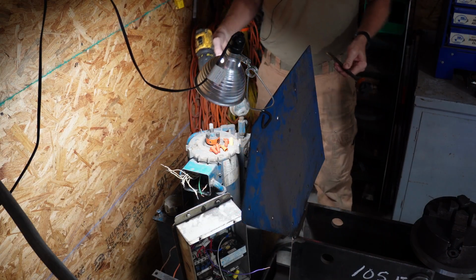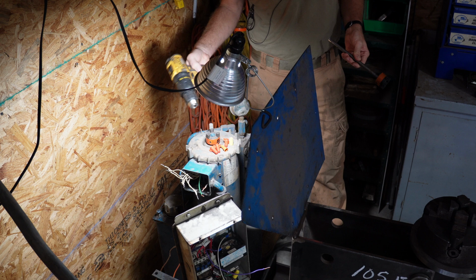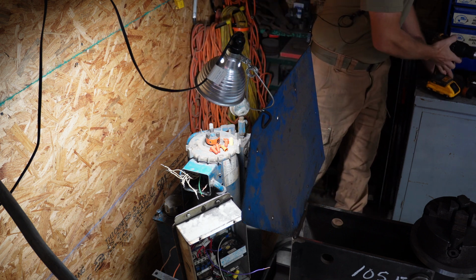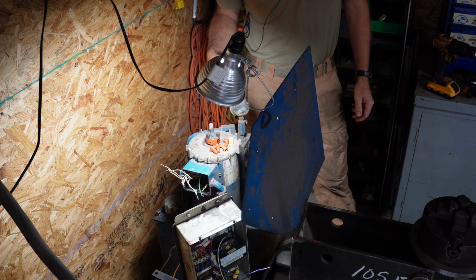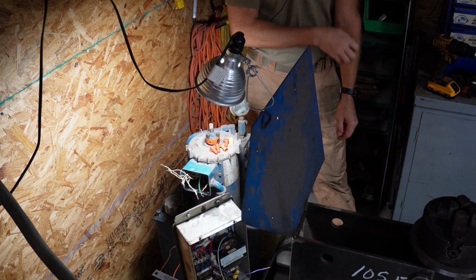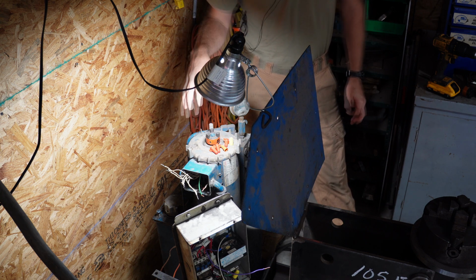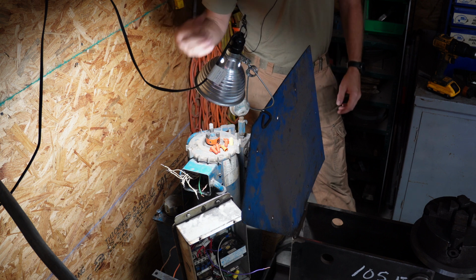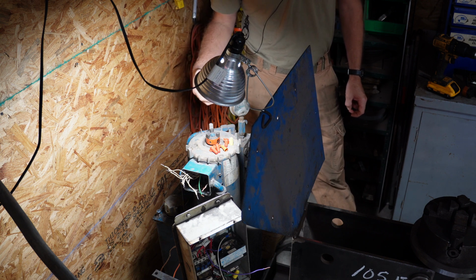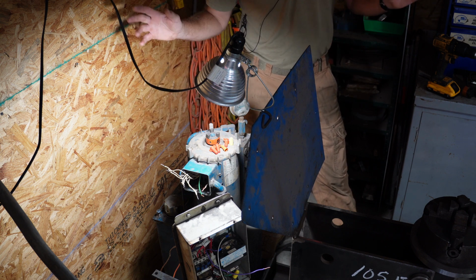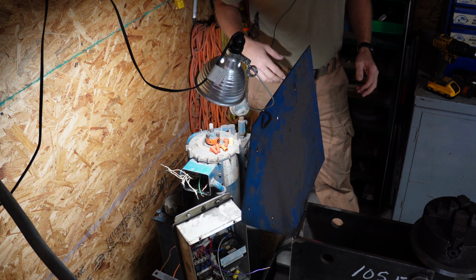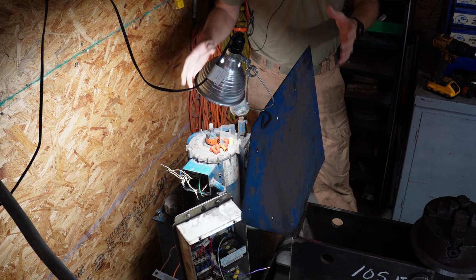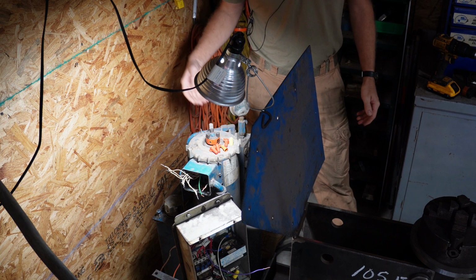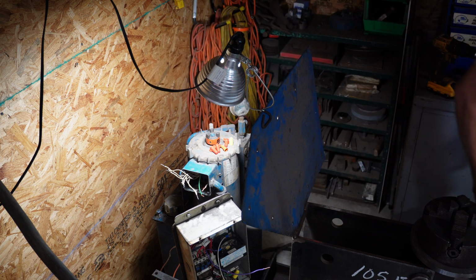Now there's a lot of resistance there. I actually let a little smoke out of this poor DeWalt. But if that drill can do it, a 3 horsepower motor should be able to spin that thing up. Now I know there's a lot of resistance on startup that's causing too much current, and that's why the VFD is getting all pissy. So something is, I don't know, something's just not quite right, and that's why we're going through this troubleshooting little by little.